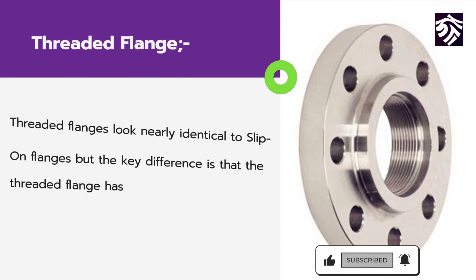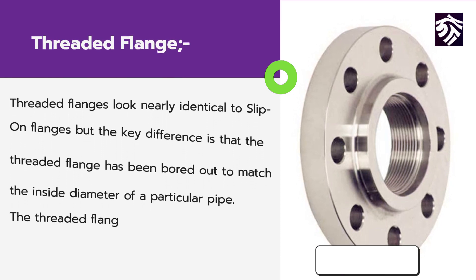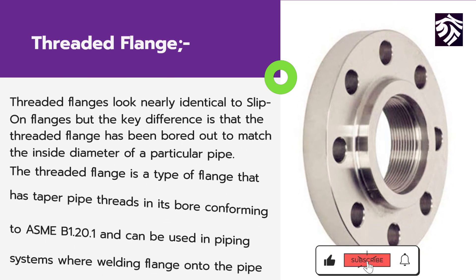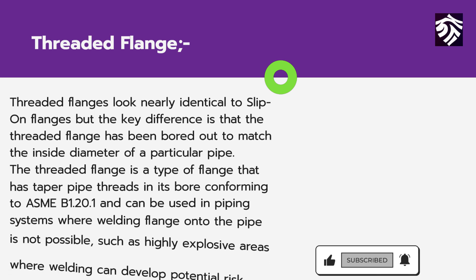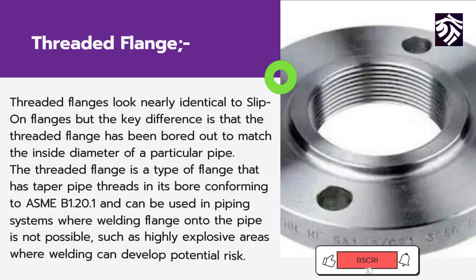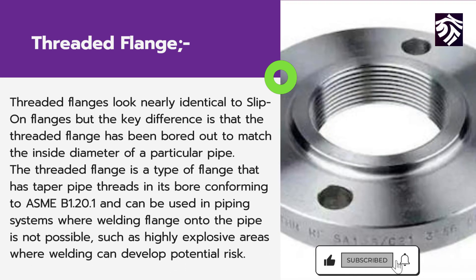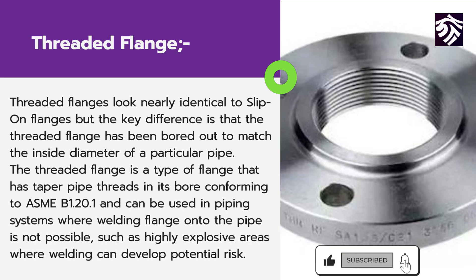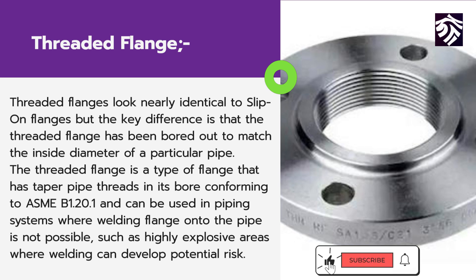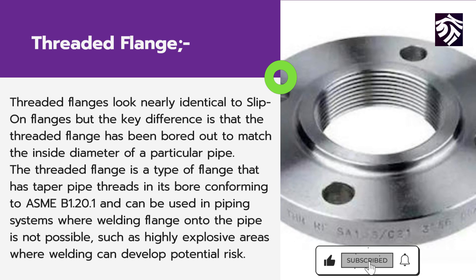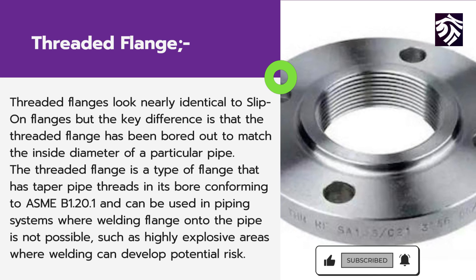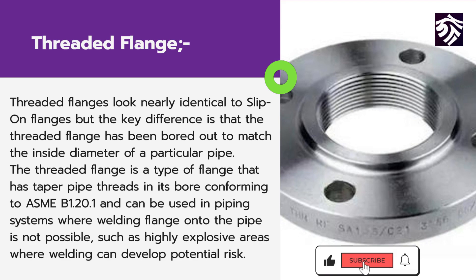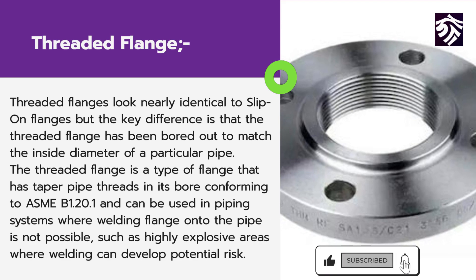Another common type of flange is the threaded flange. Threaded flanges look nearly identical to slip-on flanges, but the key difference is that the threaded flange has been bored out to match the inside diameter of a particular pipe. The threaded flange has tapered pipe threads in its bore conforming to ASME B1.20.1, and can be used in piping systems where welding the flange onto the pipe is not possible, such as in highly explosive areas where welding can develop a potential risk.